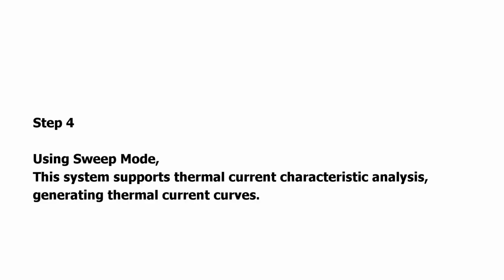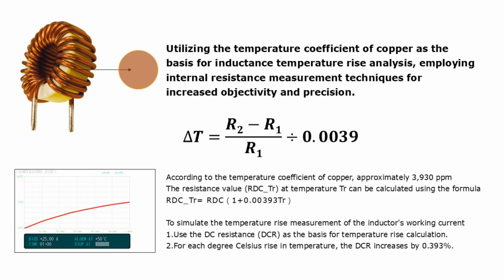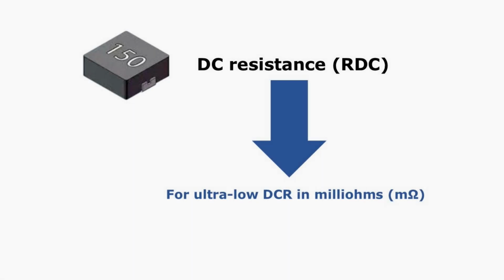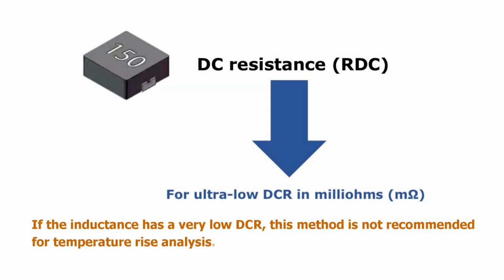This system supports thermal current characteristic analysis, generating thermal current curves. The inductance temperature rise analysis is based on the temperature coefficient of copper, using internal resistance measurement technology for more objective and precise results. It is important to note that if the inductance has a very low DC resistance, this measurement method is not recommended for analyzing the temperature rise current characteristics.